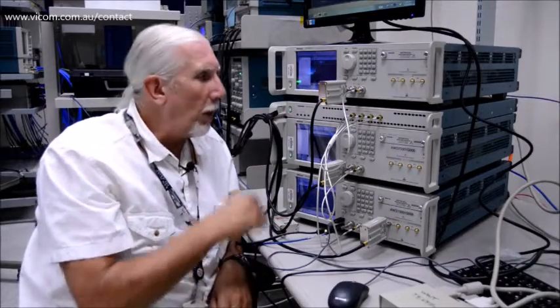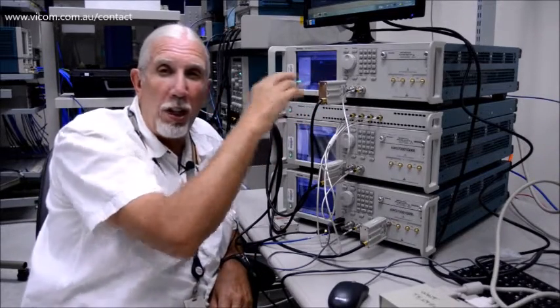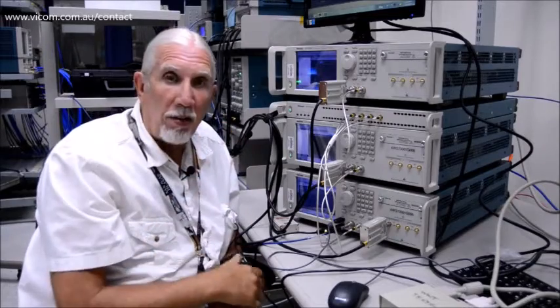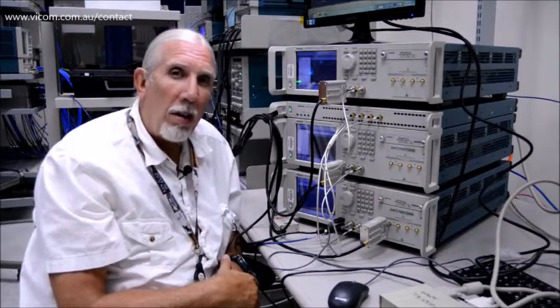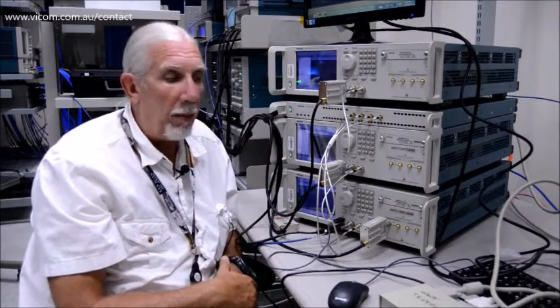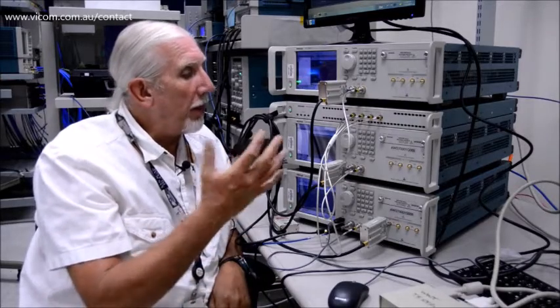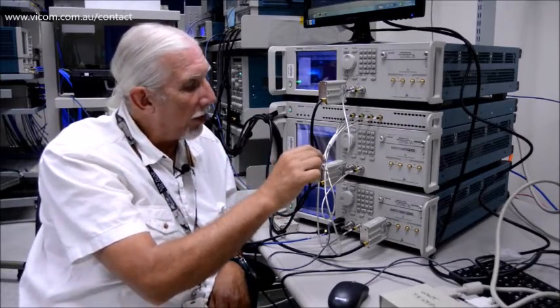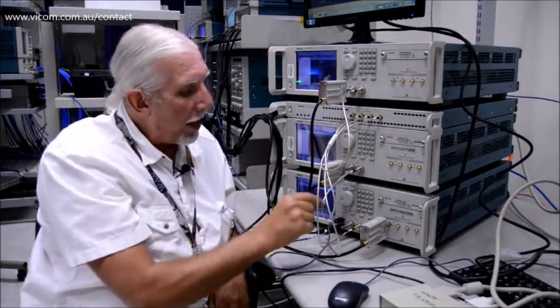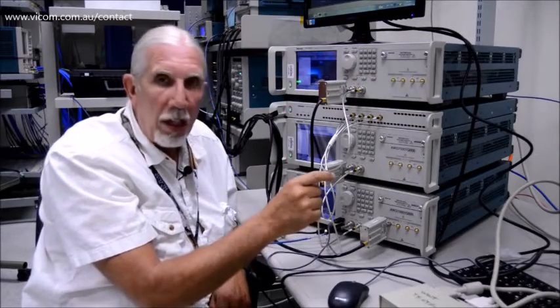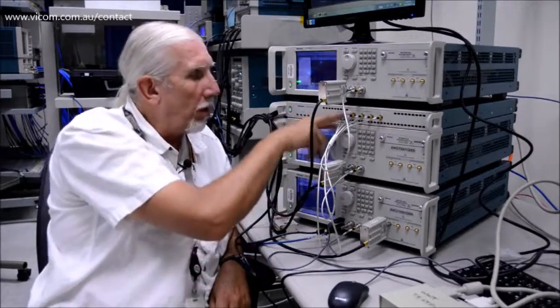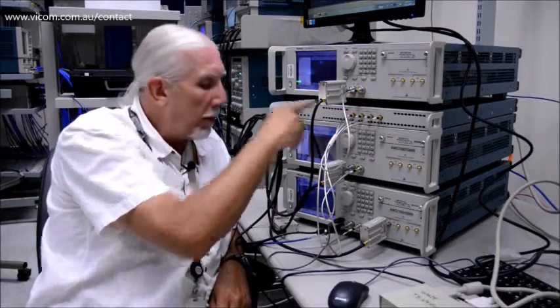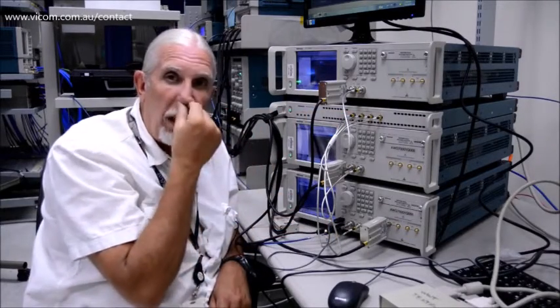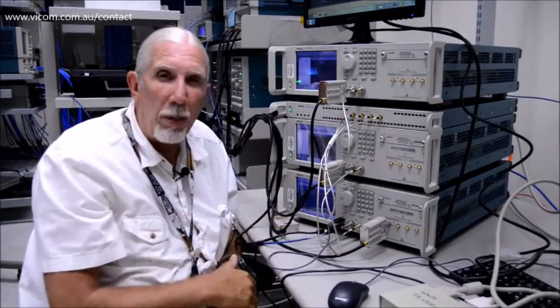This is very critical for many applications that require more than one channel or 2 channels or up to 8 channels, depending on if you have a 2-channel AWG or a single-channel AWG. Basically, the configuration is, from the front panel here, we just have the calibration cables connected from the ports of the sync hub to each of the channels of the AWG, and this is just used for calibration.